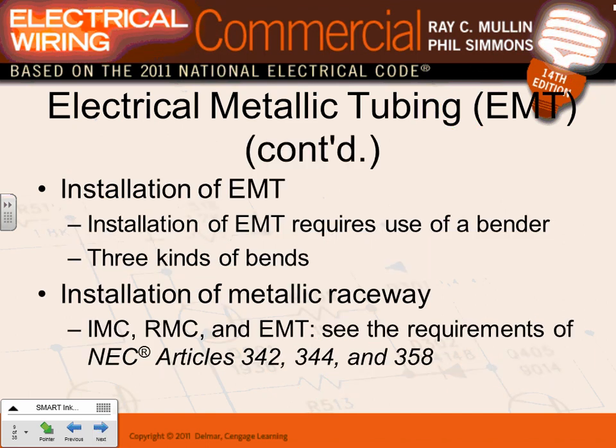You can bend EMT - it's easy. There are three kinds of bends: stub-ups, back-to-back, and three-point and four-point saddles. Where do you install EMT? Can you bury a steel EMT conduit? Yes. Is it a good idea? No. Can you use EMT outdoors? Yes, they're rated for outdoor use. Use compression fittings instead of set screws when using them outside.